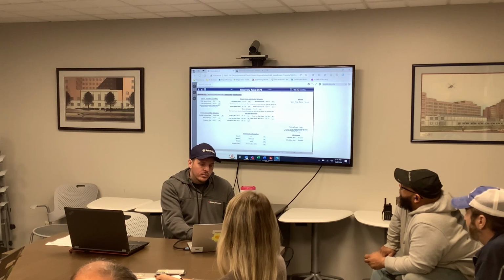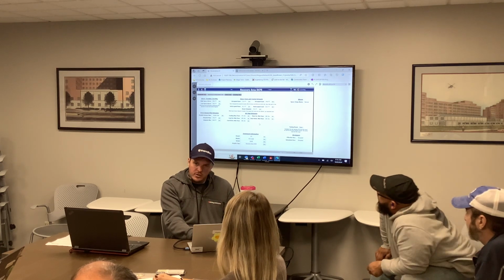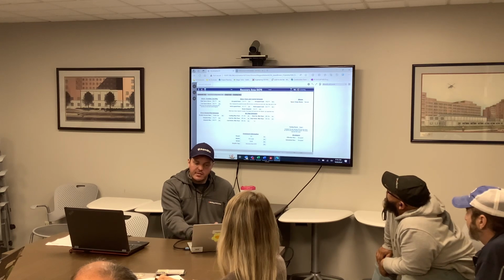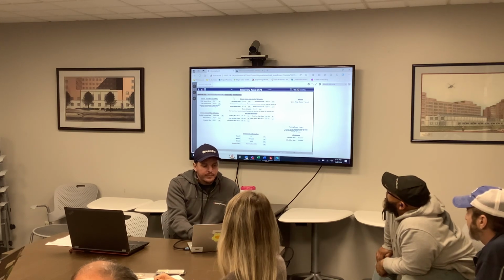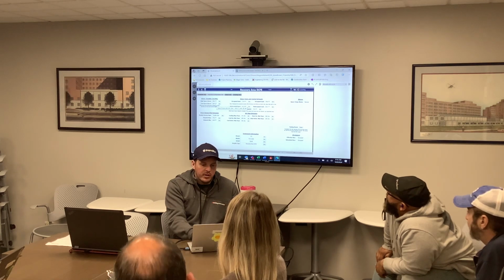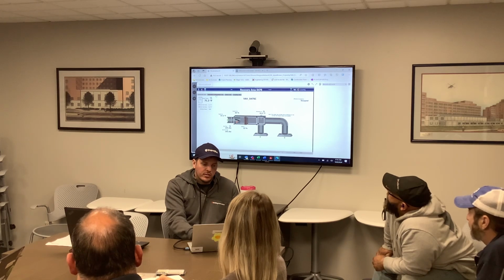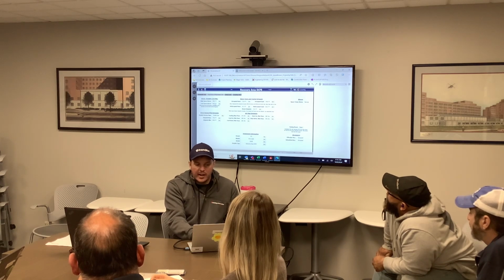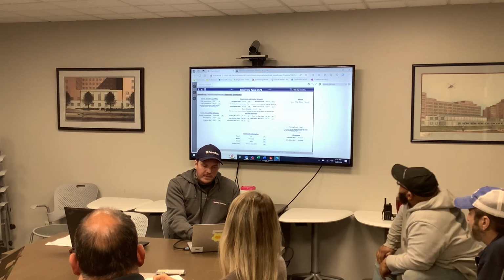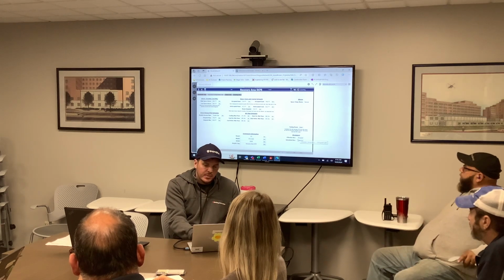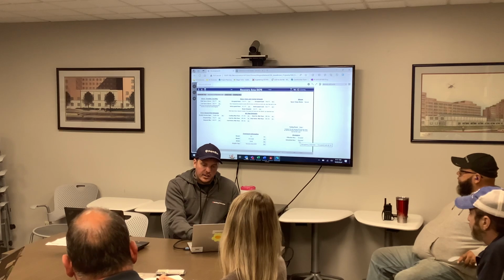The airflow set points you don't want to set or change, those are set by the balancer, but I have them out here just in case you want to see them. You have your high space temp alarm and your low space temp alarm. These are the points that trigger an alarm, so if it's higher than 85 or less than 60. Again, you have your effective occupancy and then your scheduled occupancy.